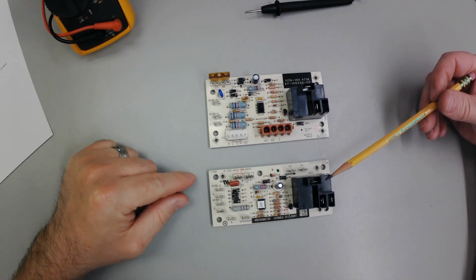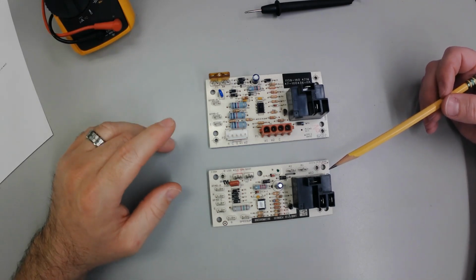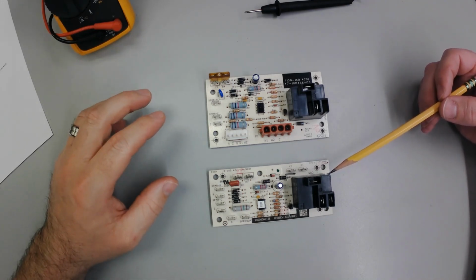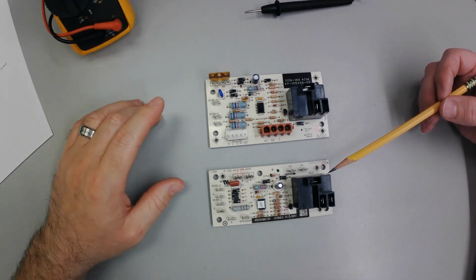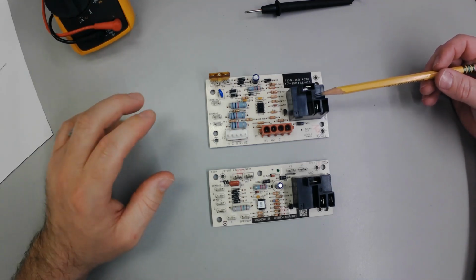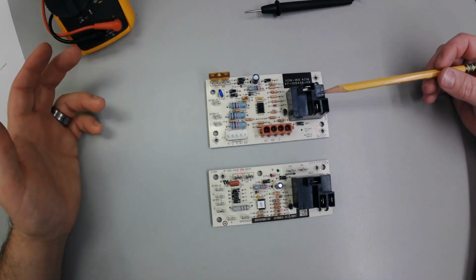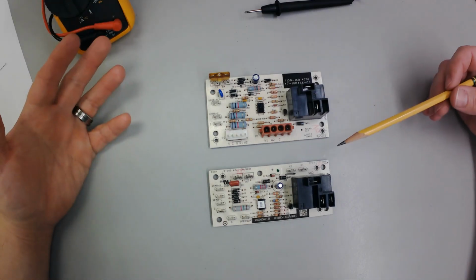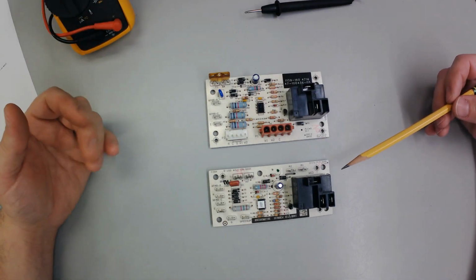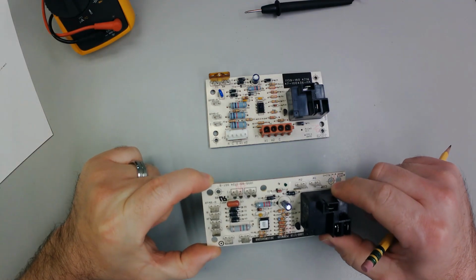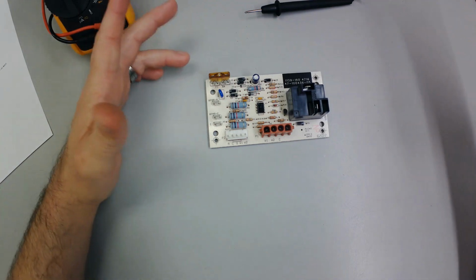The Goodman units that we have here have a high, medium, and low speed. So you'll see a black wire for high, blue for medium, and red for low. I do have a Rheem that has a 3-speed motor in it, and I've got one that's got a 2-speed motor in it. So either way, you're probably going to see this with a PSC motor. All right, so look at the Goodman video if you haven't. I like it, but you know, I'm weird like that.